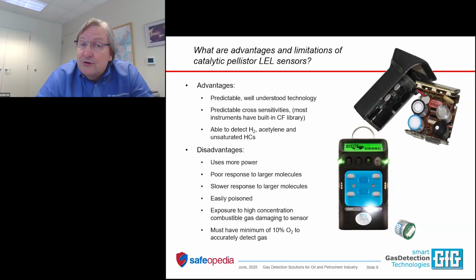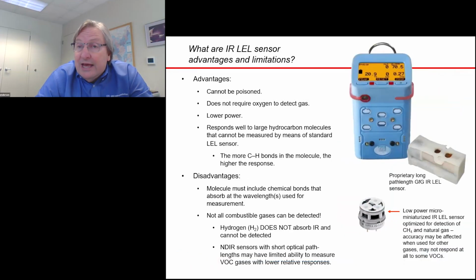Another really important thing about the catalytic LEL sensor is that it is capable of being used to measure acetylene and especially hydrogen. Hydrogen is pretty common out there. So if you have the presence of hydrogen, you need to do something to measure it. You can measure it with an electrochemical sensor, or you can measure it with a catalytic LEL sensor, but you're not going to be able to measure it with an infrared LEL sensor.